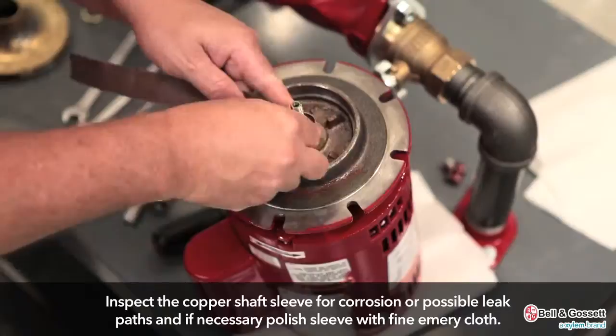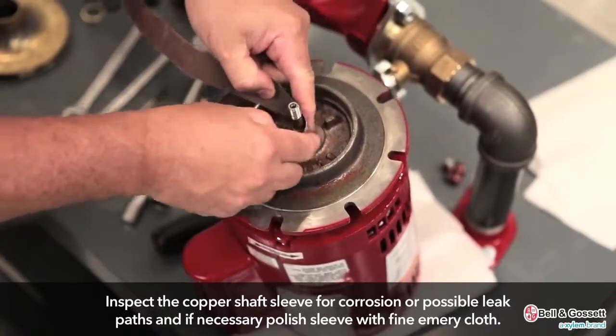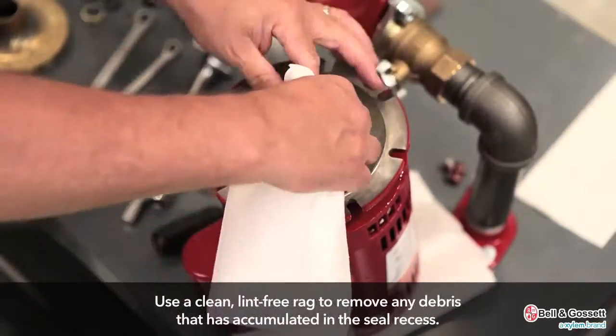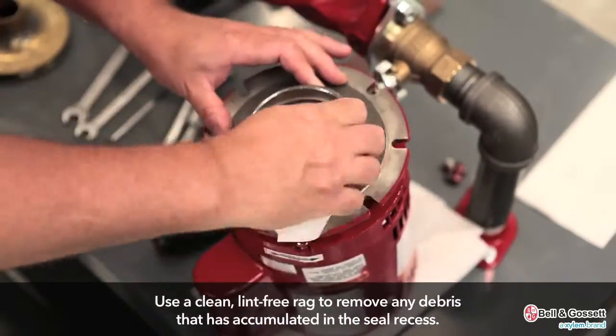Inspect the copper shaft sleeve for corrosion or possible leak paths and, if necessary, polish the sleeve with a fine emery cloth. Use a clean, lint-free rag in order to remove any debris that has accumulated in the seal recess.